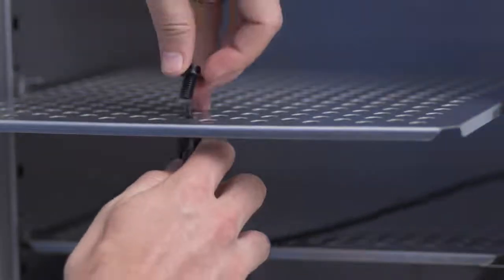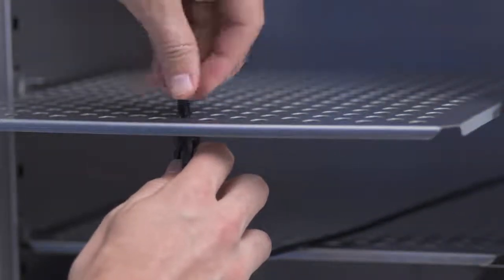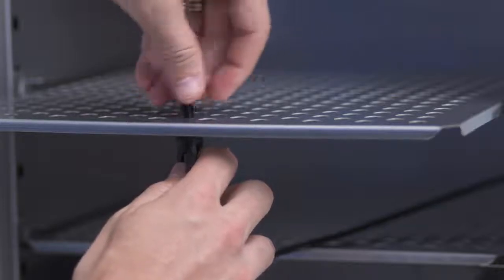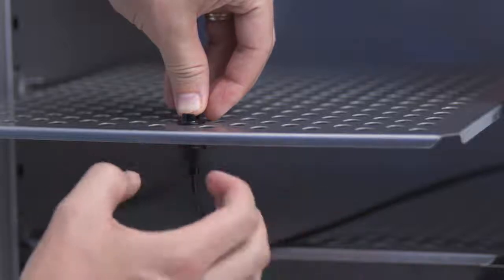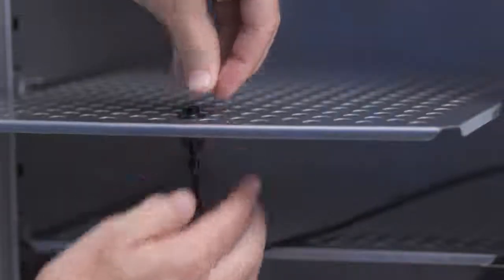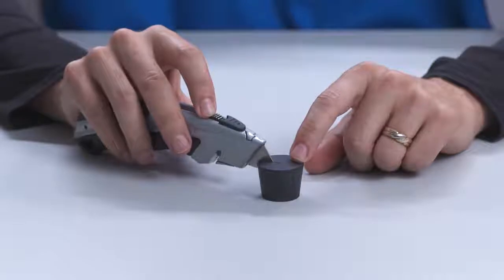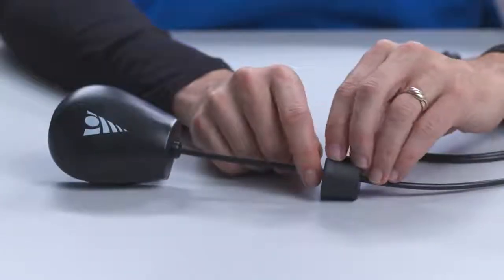For cabinet-style incubators, feed the TrakPod's fiber optic cable through the incubator's access port. Access ports are typically on the side or the back of the incubator. Loosely connect the fixture and wing nut into the hole of your incubator's shelf. Then thread the fixture onto the fiber optic until it is fully connected. Finally, tighten the wing nut against the bottom of the shelf to hold the unit in place on the incubator shelf. If you need to, carefully cut a slit into the stopper to fit it around the fiber optic. Then, seal the incubator access port with the stopper.